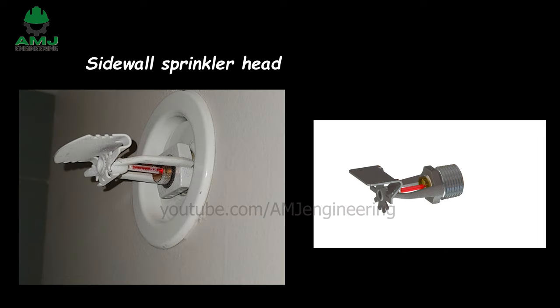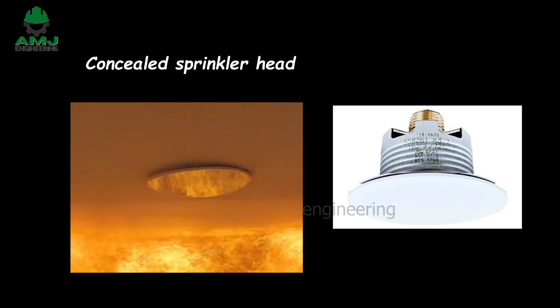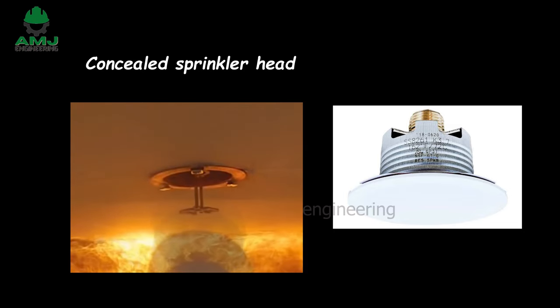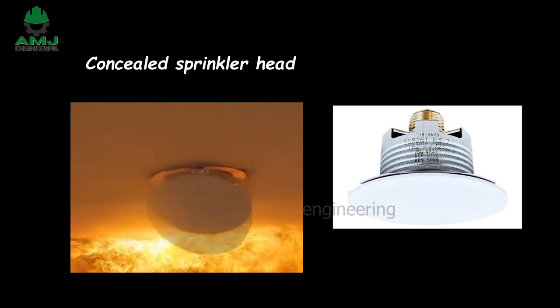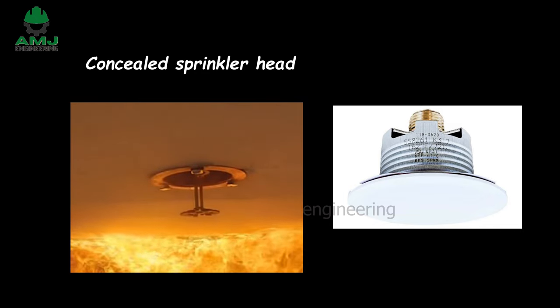Sidewall sprinkler heads protrude horizontally out of the wall parallel to the floor, rather than descending from the ceiling or mounted on a pipe pointing upward. Sidewall sprinklers are ideal for small spaces such as hallways, spaces with obstructions, and where ceiling piping is not available. Concealed sprinkler head: a heat-sensitive plate detaches at temperatures roughly 20 degrees lower than the sprinkler head, allowing the concealed sprinkler's deflector to drop and the head to activate.